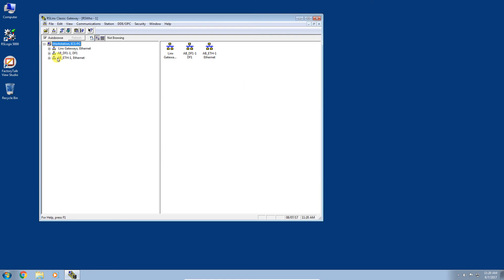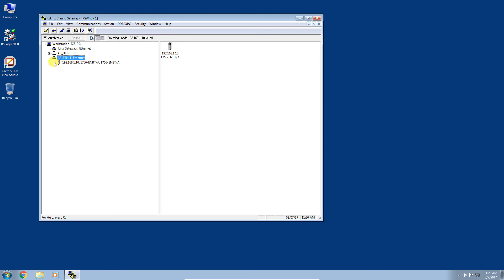You can see it immediately shows up in our driver list. I'll highlight this driver, and with auto-browse selected it starts browsing — meaning it's actively scanning that driver. I'll drill down, and you can see my Ethernet bridge module is communicating. Drilling down further through the backplane, we can see everything connected there: my 1756-L61 processor currently resides in slot 0, and my Ethernet bridge is in slot 1. That all looks good.